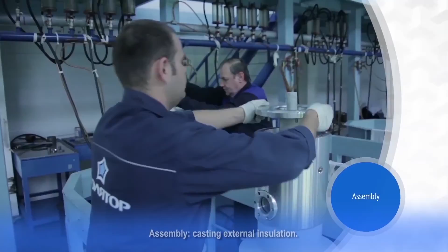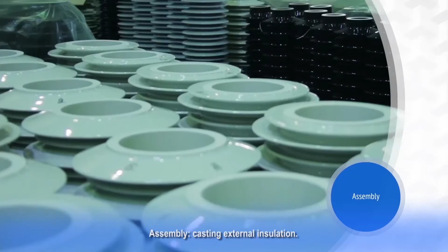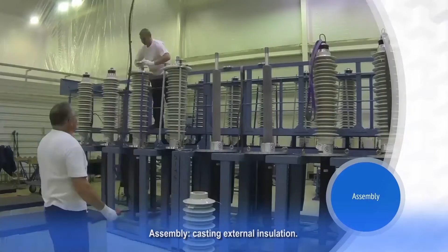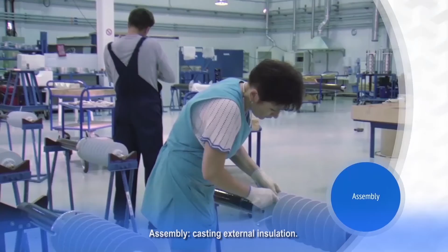The next step in producing a bushing is assembly. Ceramic or resin insulation is used for the external part. Bushings with ceramic insulation are filled with either oil or dry mass. In most designs, the external insulation is made of a special silicone rubber by casting it on the solid internal insulation with subsequent thermal curing.